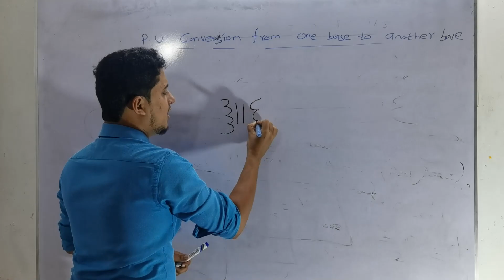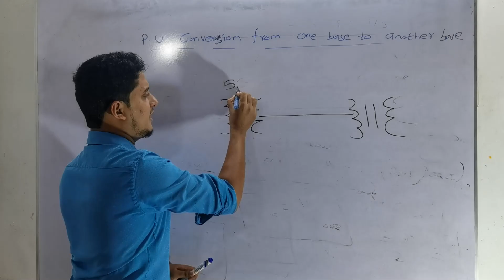I consider two different transformers. These two transformers are defined with two different base values. This transformer is defined with S1 base value of apparent power, and this transformer's apparent power is S2 base value. So this transformer's per unit value, which is mentioned in the nameplate of the transformer, is defined with the S1 base value.